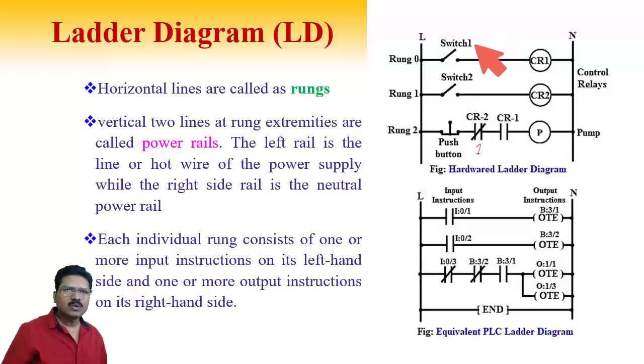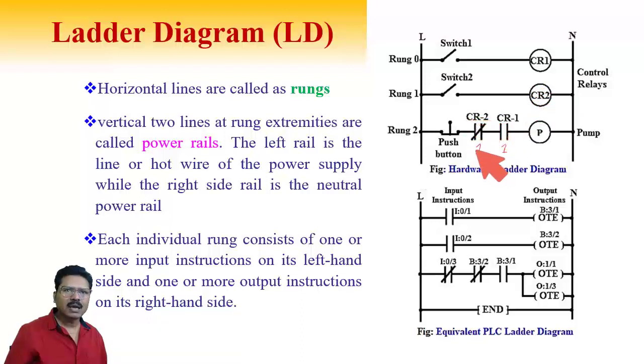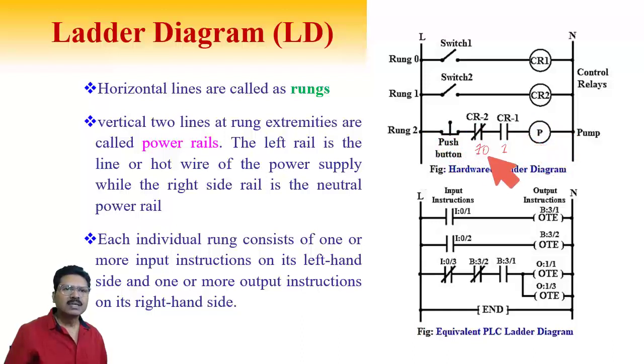When Switch 1 is pressed, the coil CR1 is energized and logic becomes ON, so the pump gets power through that line and runs. To stop: when Switch 2 is pressed, relay coil CR2 is energized, and its contact opens — acting like an inverter or NOT gate — cutting power to the pump so it stops. Similarly, pressing the push button cuts power and the pump stops.